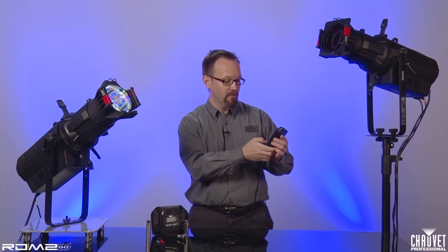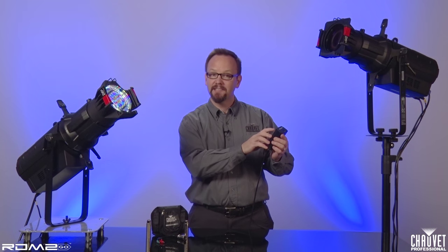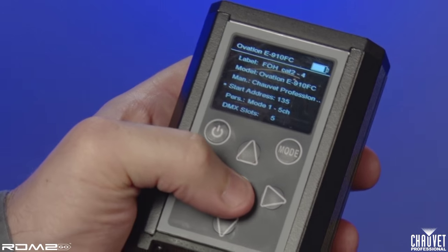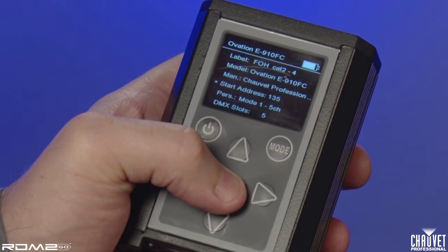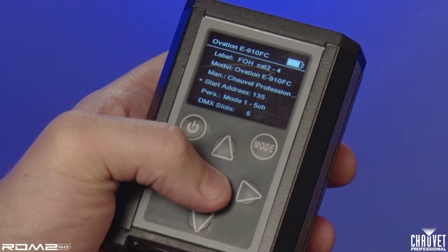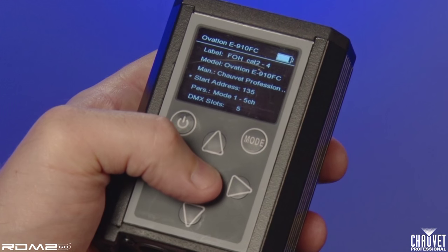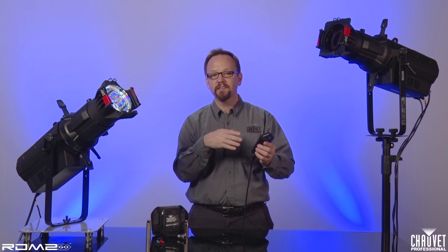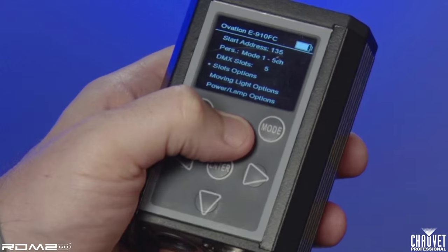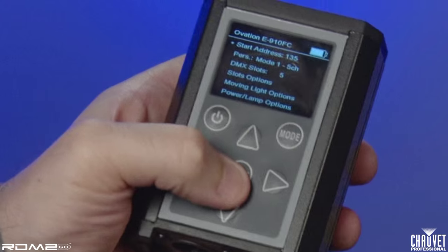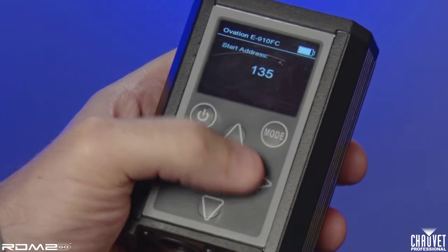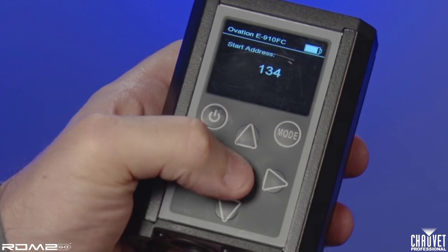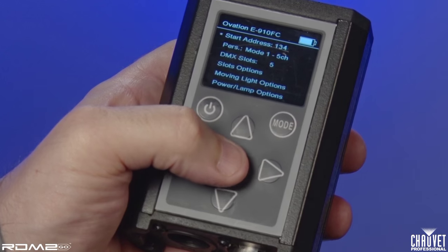If I select fixture number one, I can see the label, the model — Ovation E910FC — the manufacturer, Chauvet Professional, the start address, the personality mode it's in, and the number of DMX slots. These are all things that I can adjust simply by selecting, for instance, the start address, and scrolling through to choose a different DMX address. It's very simple to do.